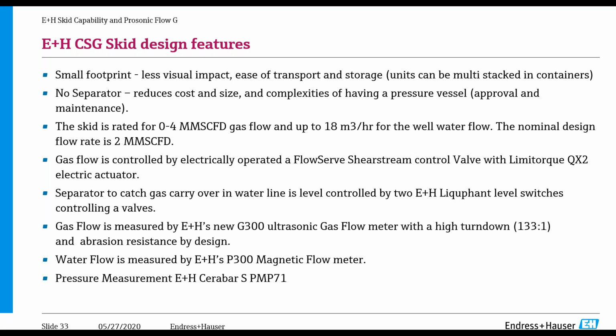Water flow is measured by the Endress+Hauser P300 magnetic flow meter. In this case, we use the P300 because we have Ethernet IP functionality on it, but we can also have HART using our P200 magnetic flow meter. On the separator itself, we monitor the pressure using our Cerabar S, which is proven technology and very reliable pressure measurement for this application.